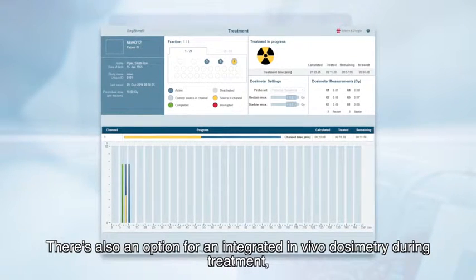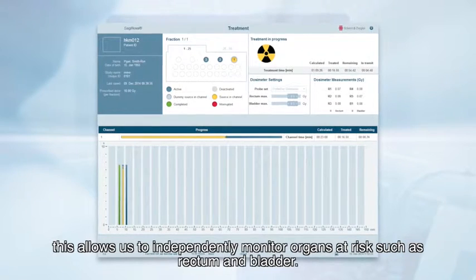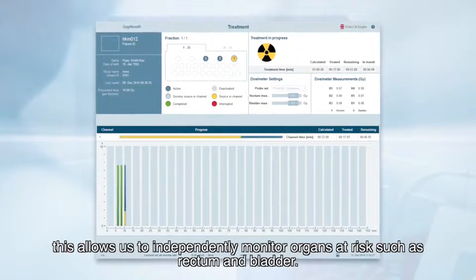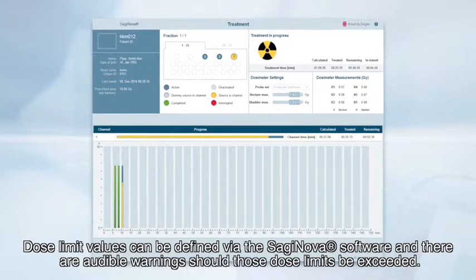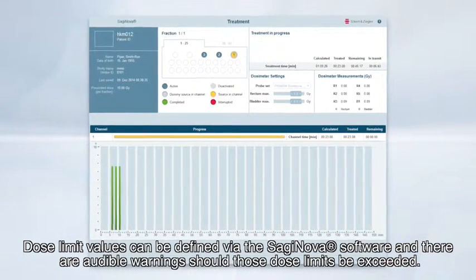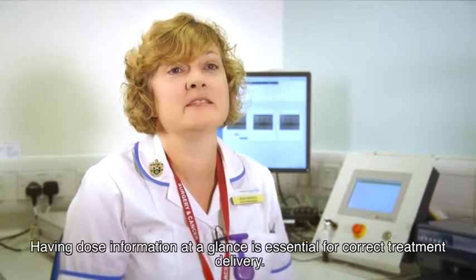There is also an option for integrated in vivo dosimetry during treatment. This allows us to independently monitor organs at risk such as rectum and bladder. Dose limit values can be defined via the SagiNova software and there are audible warnings should those dose limits be exceeded. Having dose information at a glance is essential for correct treatment delivery.